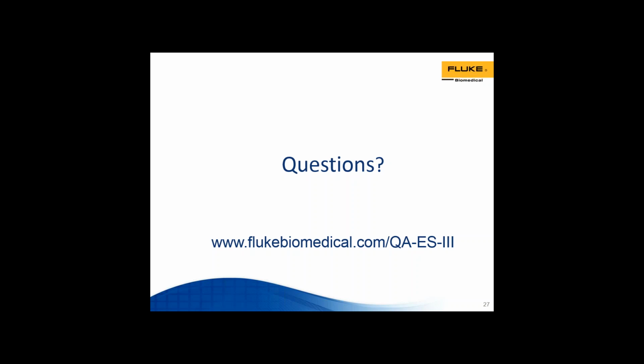All right, thank you. We had a question. How often should you calibrate your equipment? I'll take this one, Shireen. This is important because it goes to your metrology and your traceability, which is really, really important to managing the risk and keeping the patient safe who the medical device will be used on. We have a 1-year calibration cycle, and the reason for that is because as we look at all our data on each and every one of our models of test equipment, we look to see how long we could ensure that calibration is going to hold fast for you so it doesn't fall out of its own specifications, the test equipment specifications, during the calibration period.